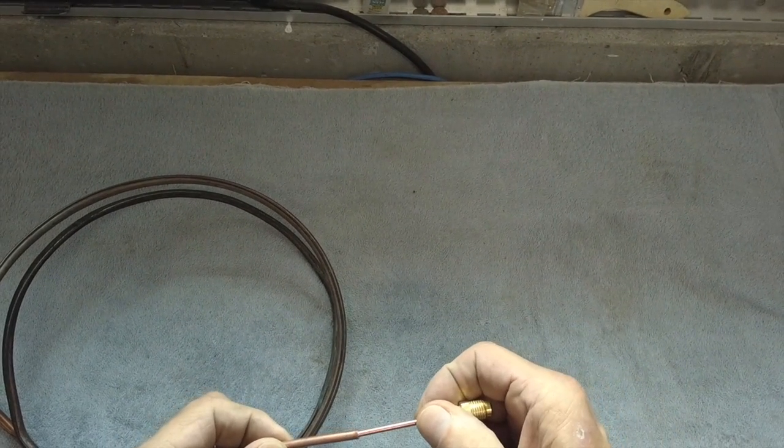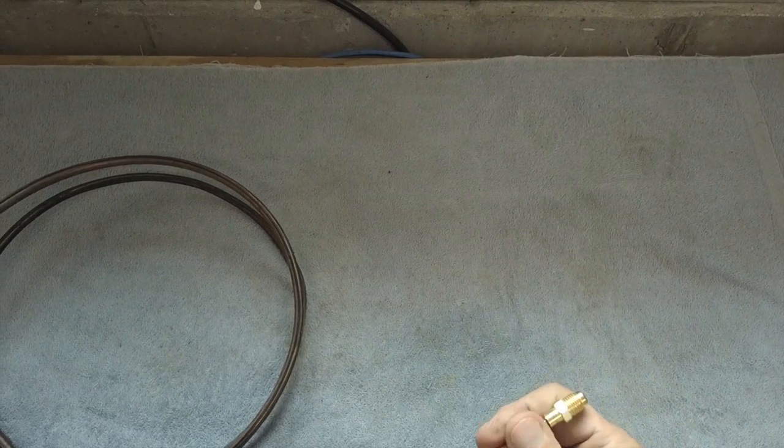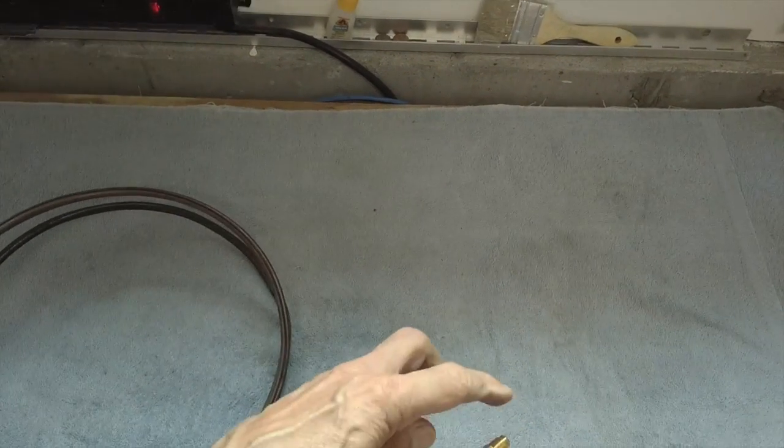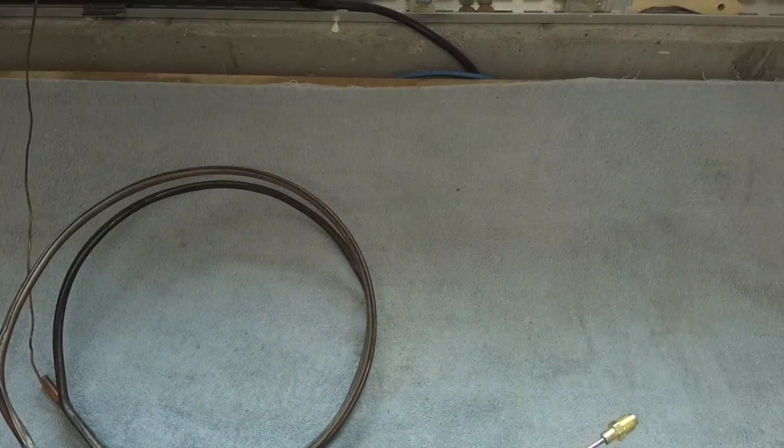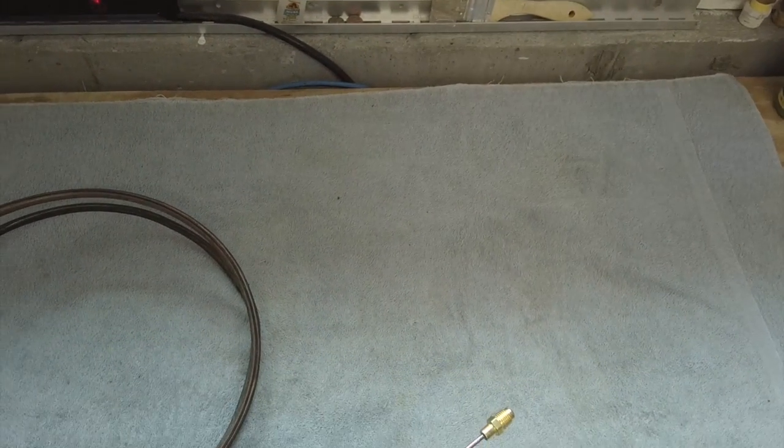We're going to solder this, sweat it together, and then we're going to sweat it onto here, into the cap tube. Then we're going to pull a deep vacuum on this tubing while we heat it to see if we can clear it up.